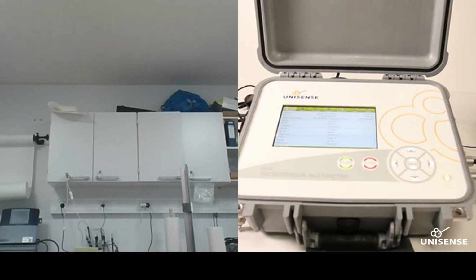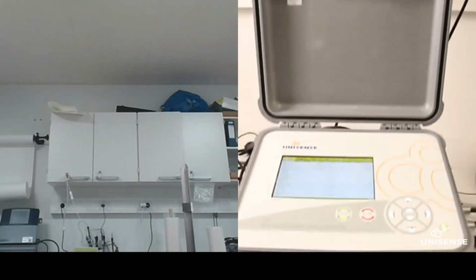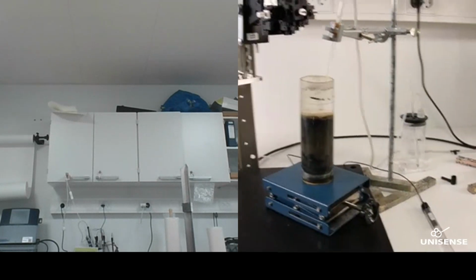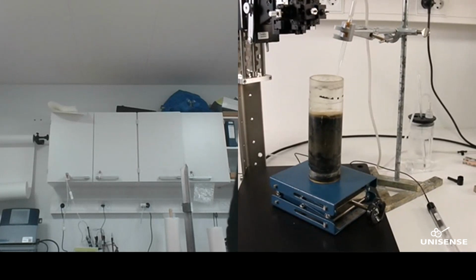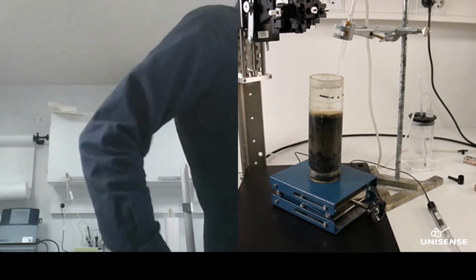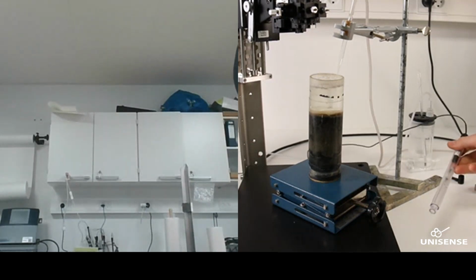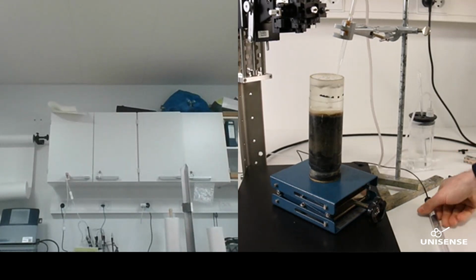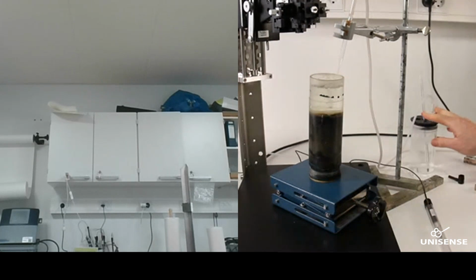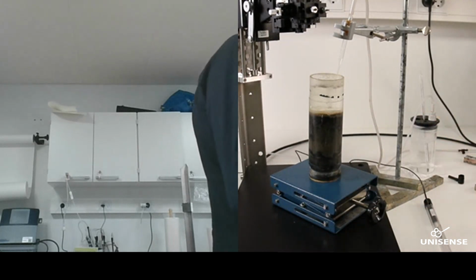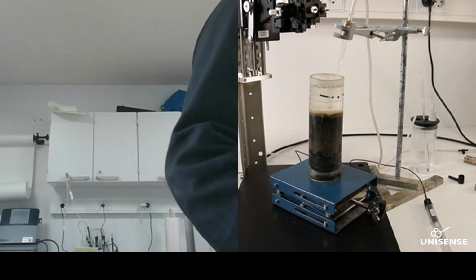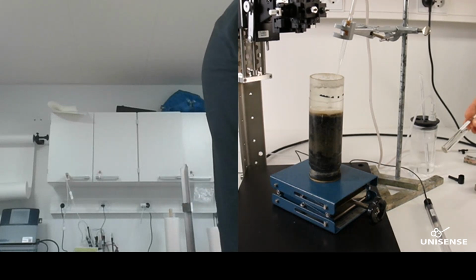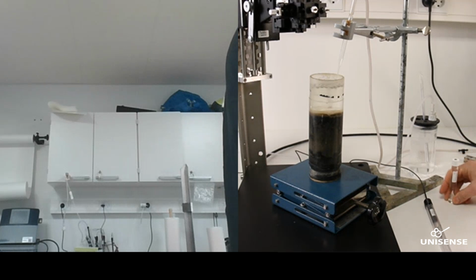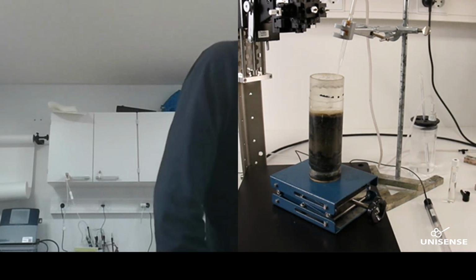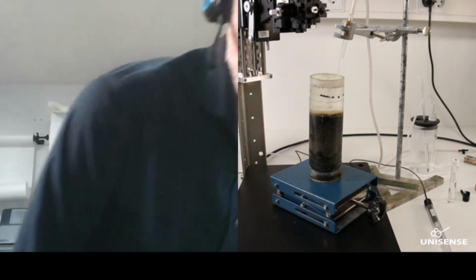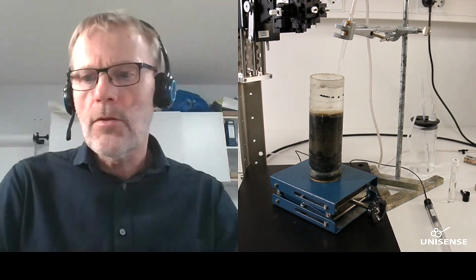Now I'll just use it as an amplifier for this setup here. What I have here is a sediment core I want to measure a profile in, and I have an oxygen sensor, which I will calibrate in a moment. I have water here in a calibration chamber being bubbled with air, which is now in equilibrium with air. And I have my calibration kit here, which is a 0 oxygen solution, and the calibration cap to put on the sensor. I'll get back to that in a moment. First, I would like to start the software.